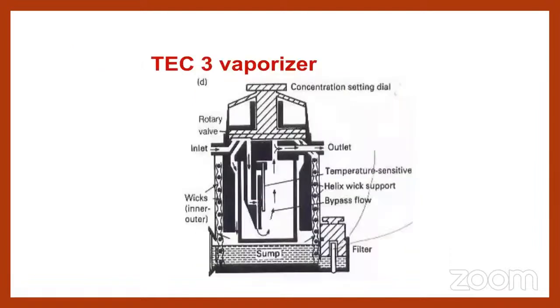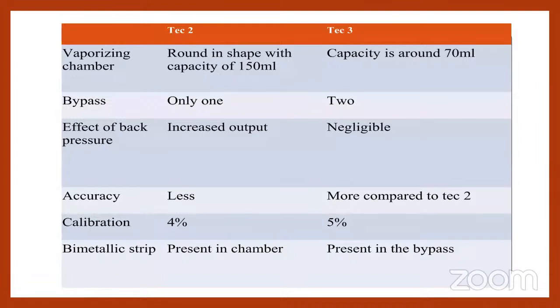The next one is the Tec 3 vaporizer. It's of variable bypass and flow over type. It's both temperature and flow compensated. It is used for halothane, isoflurane, enflurane, and fluroxene. As you can see, it has a bimetallic strip to compensate the temperature, and it has a larger bypass compared to the Tec 2 vaporizer, and the dial can be set from 0.5 to 5% of vapor that can be mixed with the fresh gas. These are the major differences between Tec 2 and Tec 3 vaporizers.